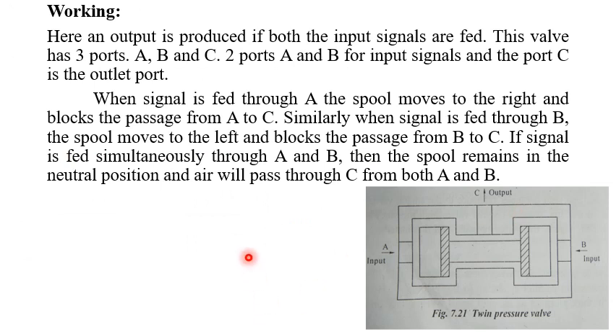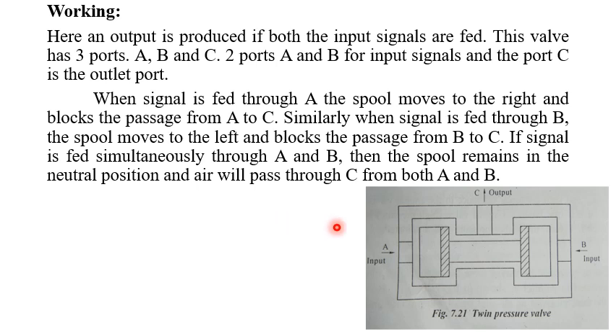The twin pressure valve has three ports: A, B, and C. A and B are the input signals; C is the outlet port. When signal is fed through A, the spool moves to the right and blocks the passage from A to C. When signal is fed through B, the spool moves left and blocks the passage from B to C. When signals are fed simultaneously through both A and B, the spool remains in the neutral position and air passes through C from both A and B.